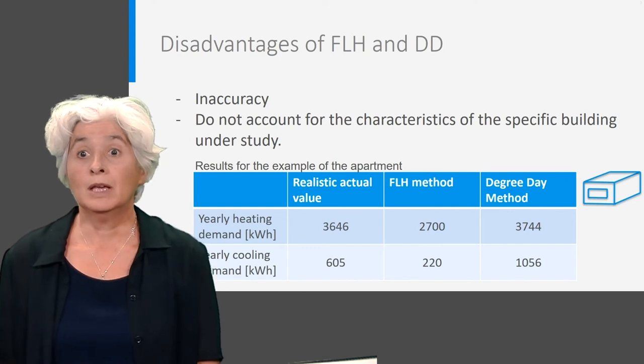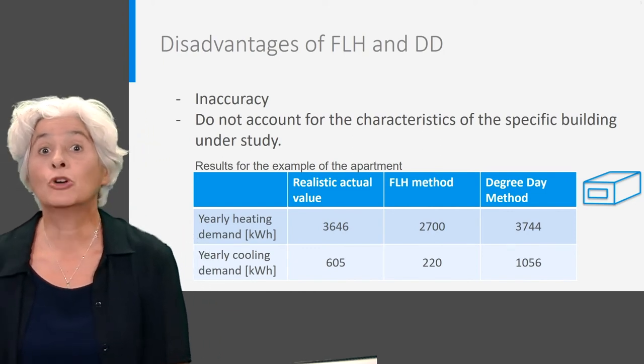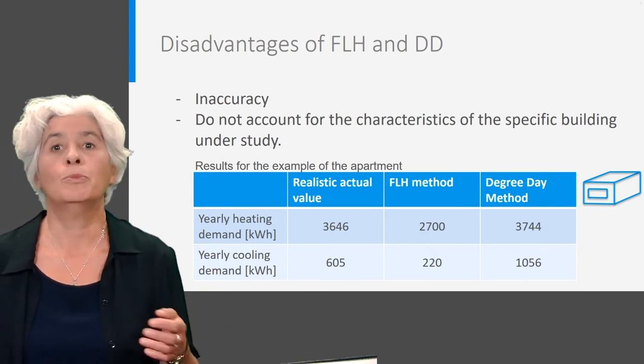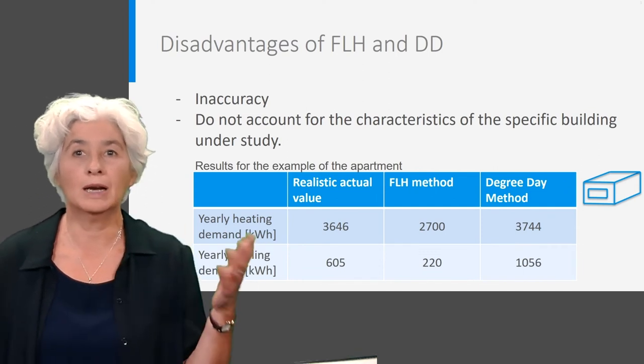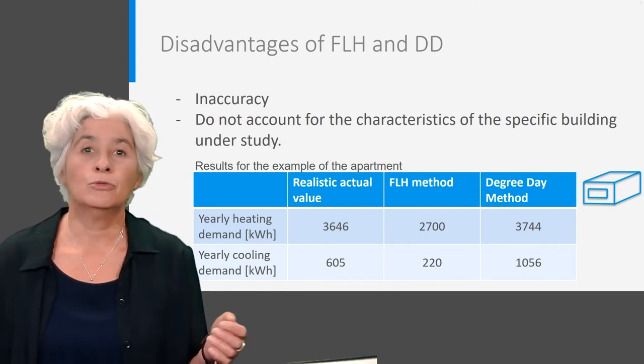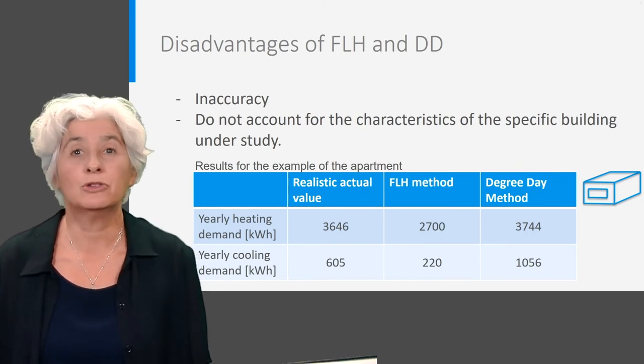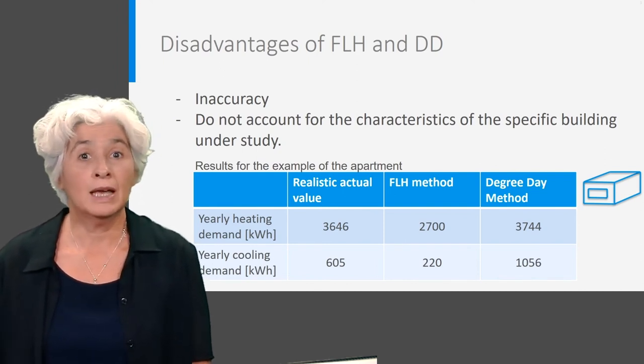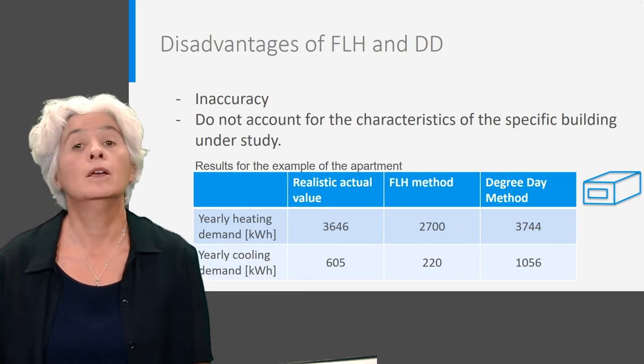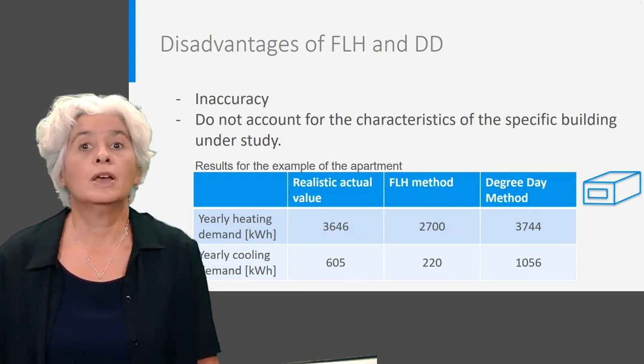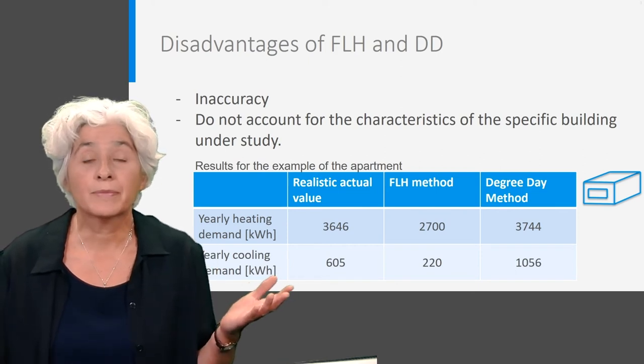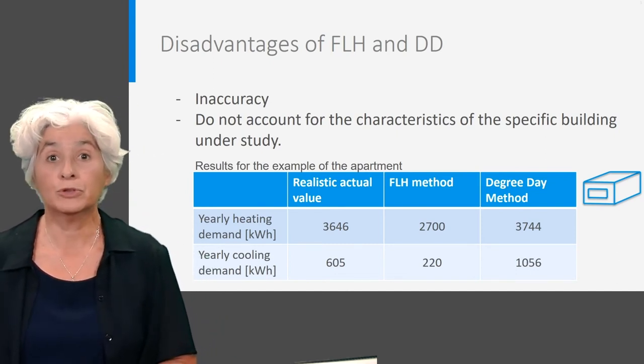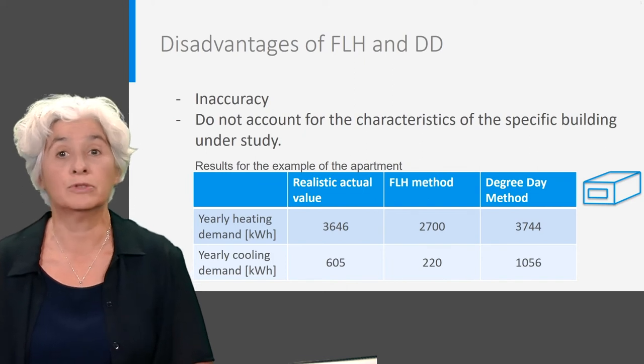The degree day method is widely used and very powerful when it comes to the normalization of energy demands in different years. It offers a good way to make fair comparisons between years and between climates. However, its application to make estimates of the yearly energy use based on nominal powers is not recommended. Although full load hours and degree days may be very useful for a quick estimate of the magnitude of the energy demand, it is evident that they are very inaccurate. The main reason for this is that they are based on averages over different buildings and do not account for the specific characteristics of the building under consideration.